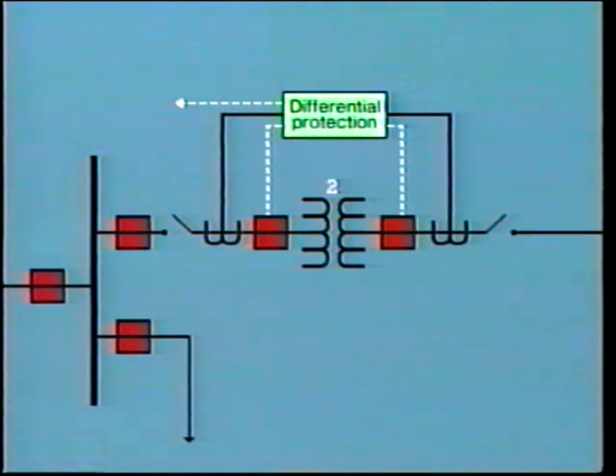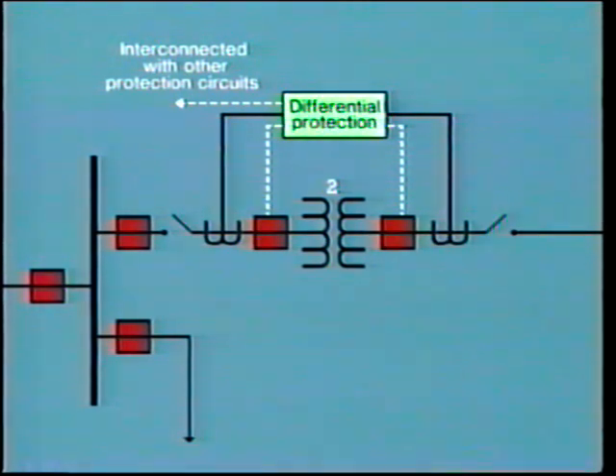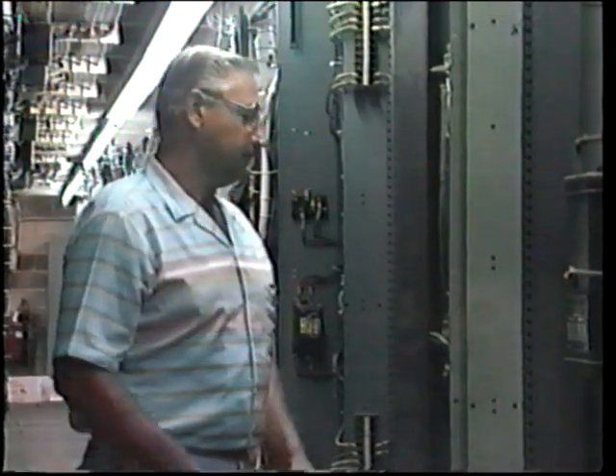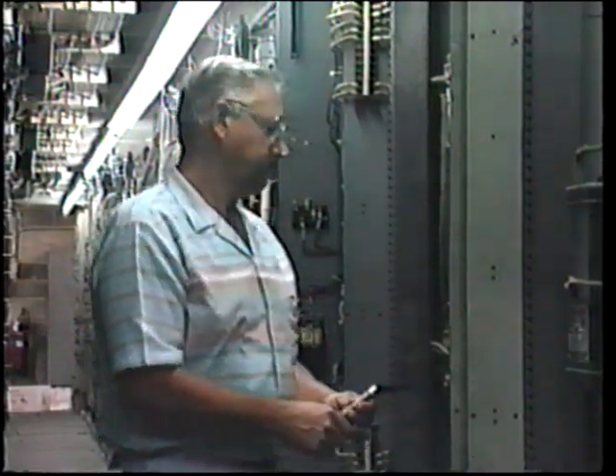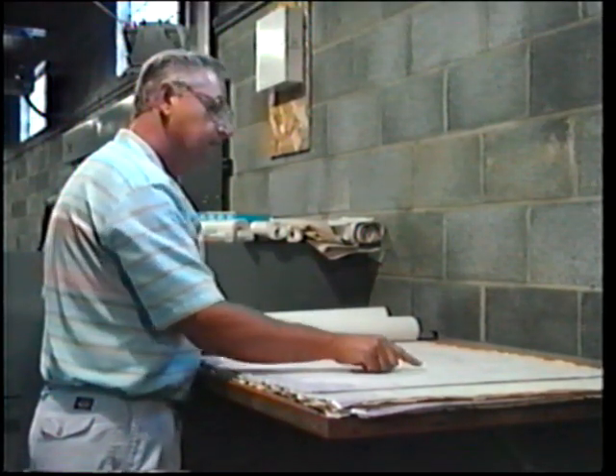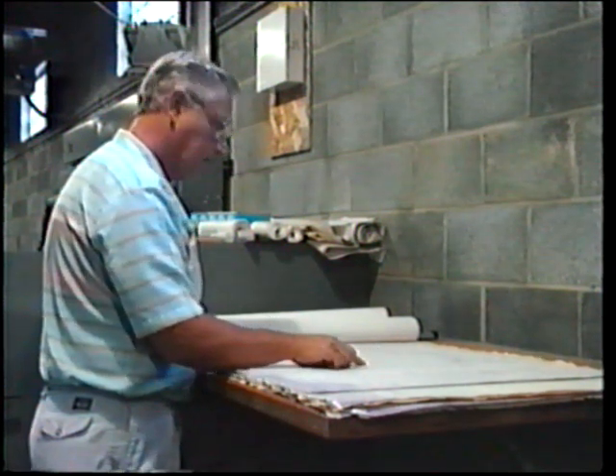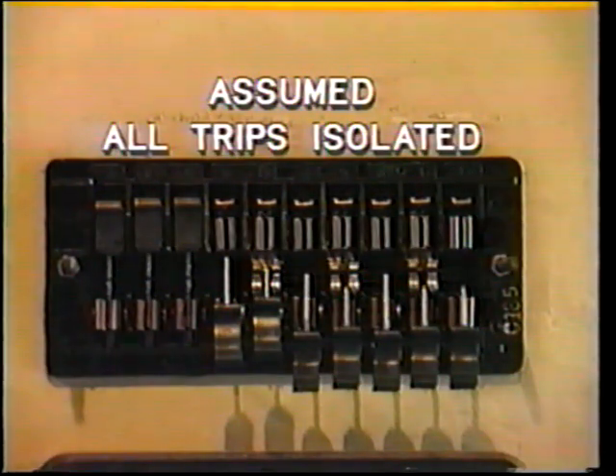Here's another incident with a similar cause. The technician was testing relays on transformer number 2, which had been isolated. However, some of the relays on this panel are interconnected with other protection circuits, such as bus protection. For this reason, the technician attempted to isolate the trip wires from the differential relays. However, the wrench he used was not suitable, so he could not remove the terminal nuts. Instead of looking for another tool, he looked at the diagram to trace the trip wires to the next connecting block. He could not find this connecting block on the relay panel, so he decided to alter his test procedure. He assumed that the isolation test device had actually isolated all trips from the relays.